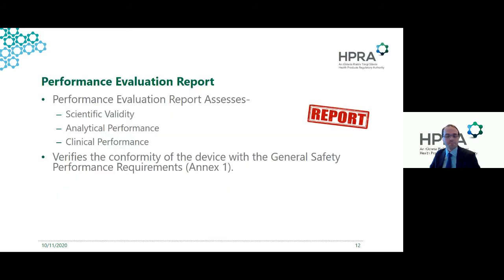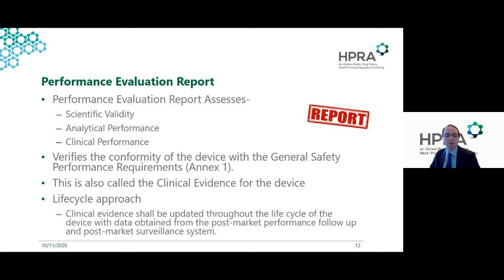The performance evaluation report is really in place to collate the data from your assessment of scientific validity, analytical performance and clinical performance, and it's there to demonstrate and verify that you've met the requirements of the general safety performance requirements in Annex 1. So this is also called your clinical evidence for your device, and it's the basis of the clinical evidence.